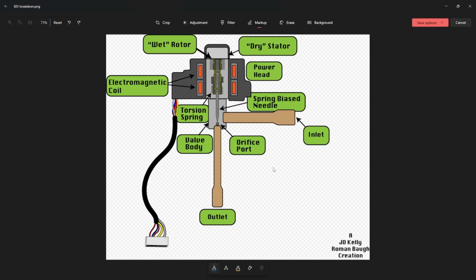Trane also has a series of pins on their board where you can actually do a test. It's 3 pins that stick off the board. One will say open. That is an O, I swear. One will say close, and the other one will say common or test. It actually says test, not common. So it'll say test. So these 3 pins are how you can actually force your EEV to drive open or closed.